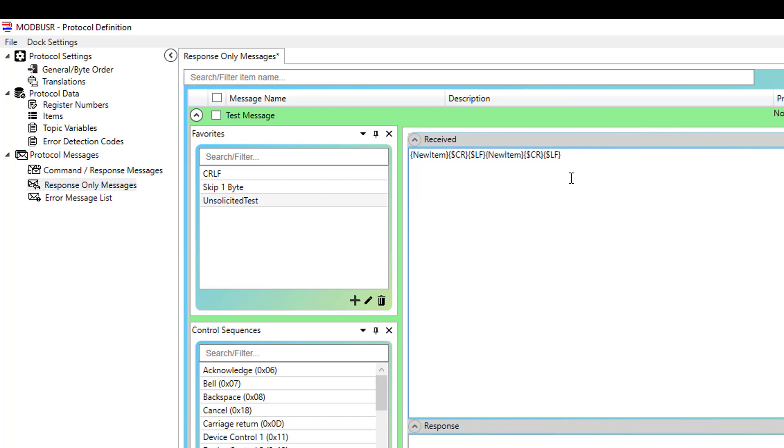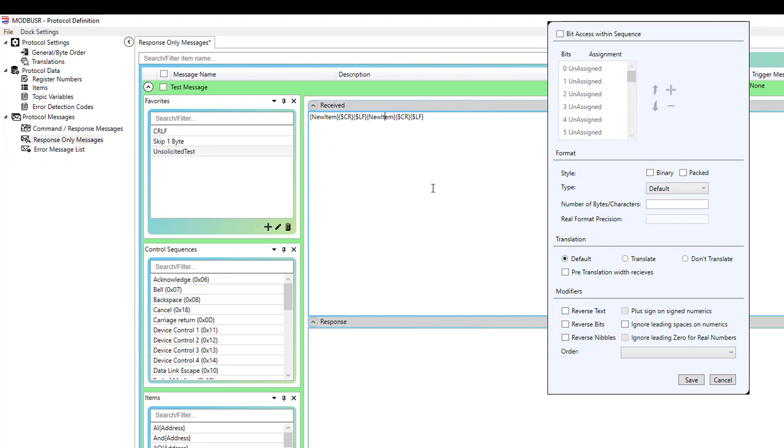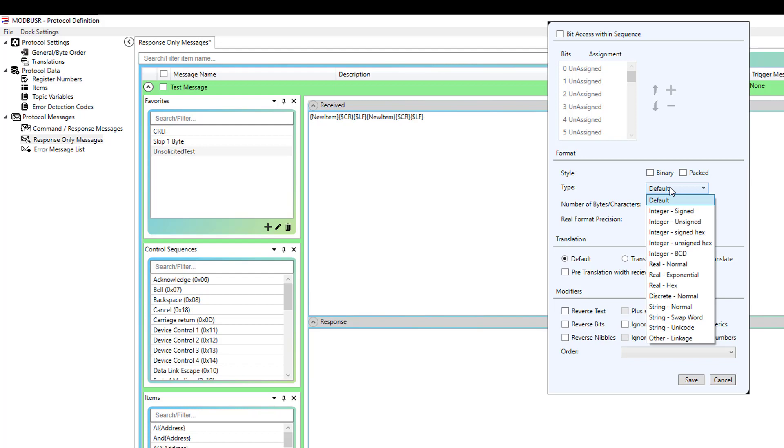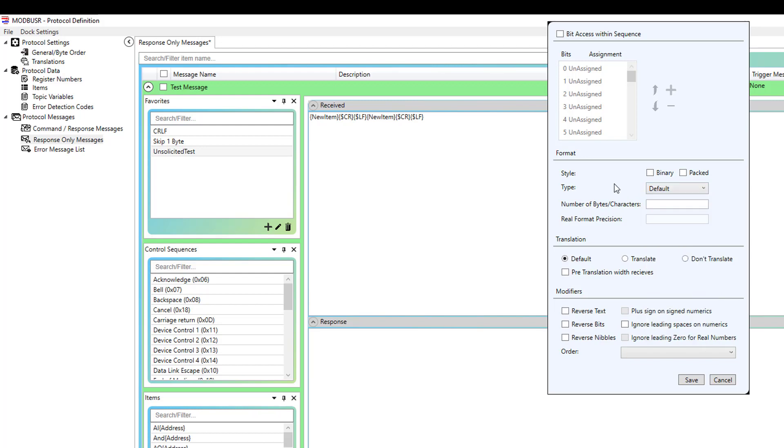One last thing I want to show you while we're in the message is you'll notice that items are added without any sort of formatting. If you're in a situation where you need to add non-default formatting, you just right-click on the sequence. And if you've used the legacy editor before, you'll be familiar with the look-and-feel settings available in there. This is where you would go if you needed to define bit access within a byte. Like, if you wanted a bit within a byte to be assigned to an item, this is where you would come to do that. This is where you go to change the number formatting for the data that's coming in for an item. For instance, if it's binary, or if it needs to be assigned integer, a real normal. If it's a real, you can define the precision. So, if I set that to real normal, you can define the number of bytes and characters in the real format precision. Whether translation should be applied or not, whether we need to reverse text, reverse bits, reverse nibbles, any of those advanced modifiers that were all available in the legacy protocol editor. Those are available here just by right-clicking on the sequence and selecting format.